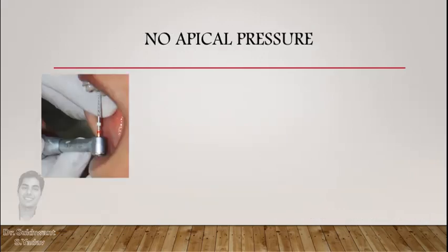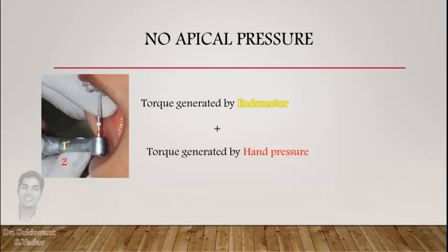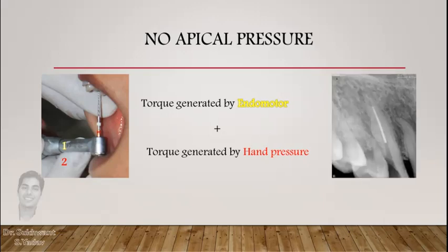Because of this torque limit, sometimes a file does not advance in the canal. In that case, do not force the instrument inside, because this extra force will be added to the safe torque limit of the endomotor and will exceed the inherent torque capacity of the instrument, resulting in deformation or fracture.